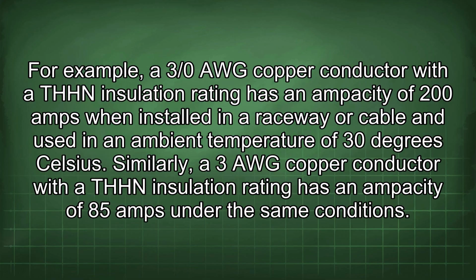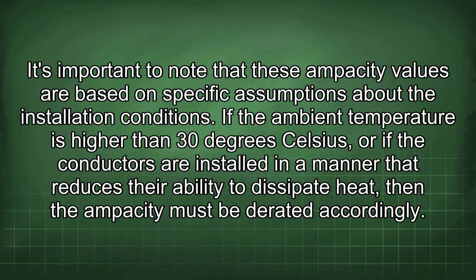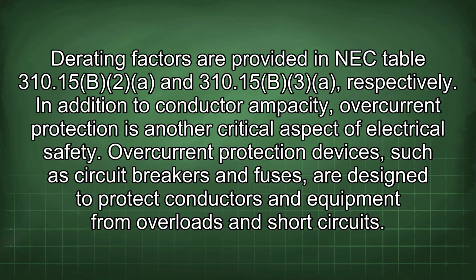Similarly, a 3 AWG copper conductor with a THHN insulation rating has an ampacity of 85 amps under the same conditions. It's important to note that these ampacity values are based on specific assumptions about the installation conditions. If the ambient temperature is higher than 30 degrees Celsius, or if the conductors are installed in a manner that reduces their ability to dissipate heat, then the ampacity must be derated accordingly.